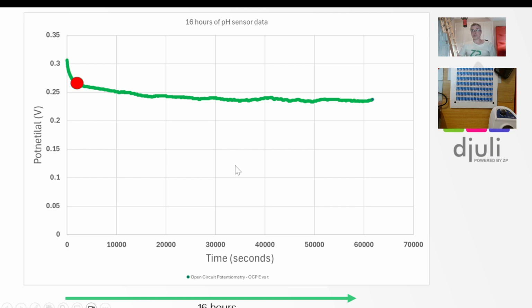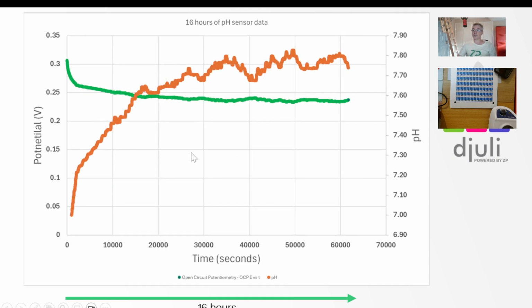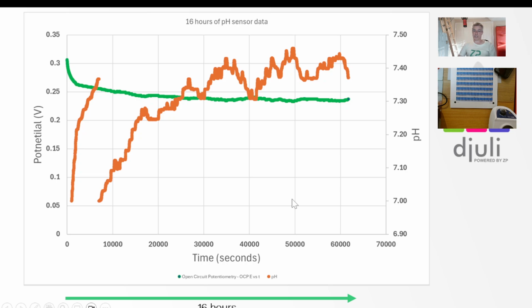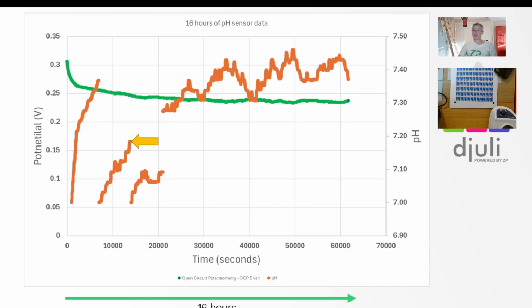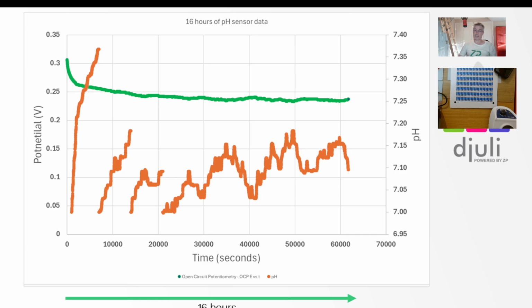And so if you could think of strategies or mitigations to deal with that early change in open circuit potential, which would reflect in a change in pH, then overall you'd have a pH signal that was much more stable. So I showed that if you just did a 1 point calibration, the pH would go from 7 to 7.8, but by coming up with a pH strategy, by doing some calibrations, you could reduce the impact of open circuit potential drift, and therefore its impact on pH, by doing a series of pH calibrations during the run.